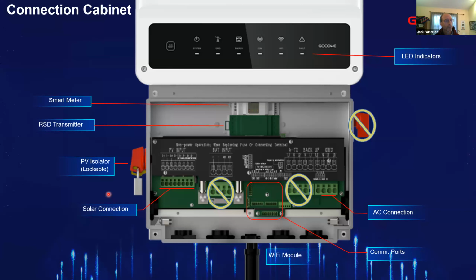This is a peek inside the inverter, the wiring compartment. It's got some of the wires, and none of the wires that were normally here that move up from the circuit board into the main electronics above are shown just for clarity. But the top device here in the center on a DIN rail is the smart meter, GoodWe's smart meter, and then the rapid shutdown device, or transmitter. If it's green, it's a Tigo. If it's gray, it's an AP Smart. And then we've got the black area here, which is just all the instructions for the terminals, just labeling what they are.